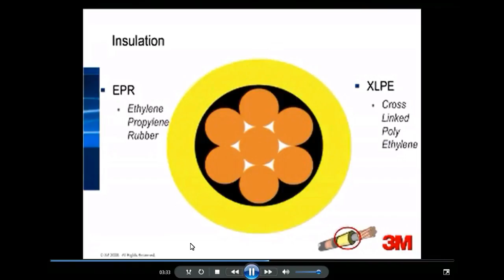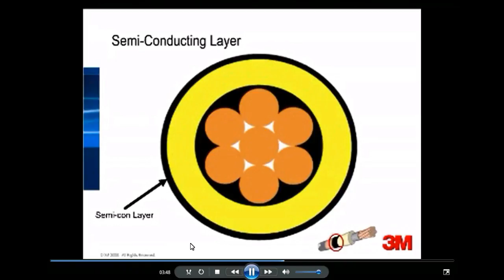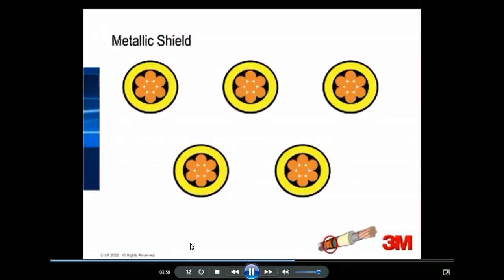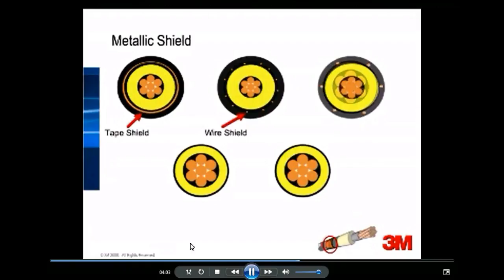The next layer is the semicon layer of the cable. The function of this layer, somewhat similar to that of the strand shield layer, is to shield the cable insulation from the air that is between the cable insulation and the metallic shield. The metallic shield is the conductive, metallic component of the cable's shielding system. It serves many different functions. It contains the electric field within the cable, provides symmetrical radial distribution of voltage stress in the insulation, limits radio interference, and reduces the hazard of shock. It also serves as a return path in the event of a short circuit, and for concentric neutral cables, it provides a neutral return path. The metallic shield must always be grounded.